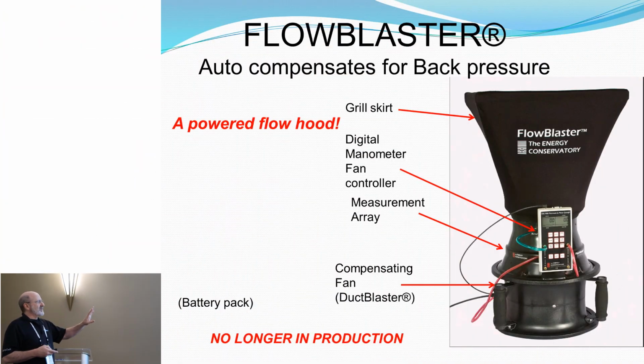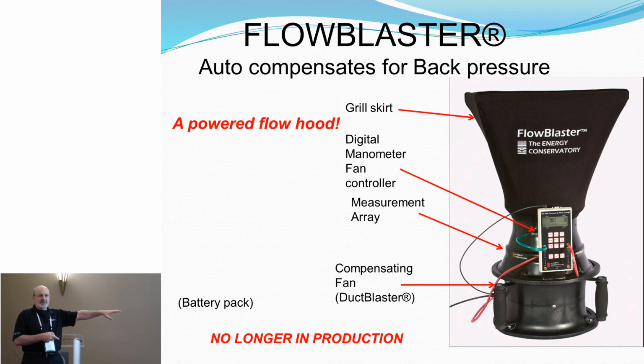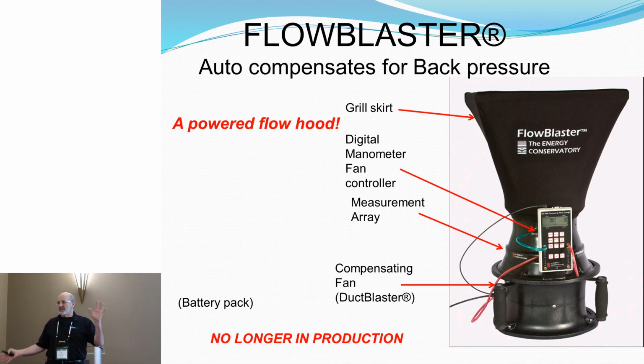I don't have time to show the comparison spreadsheet, but here's an illustration of the powered flow hood. We talked about it before. Basically a fan with a measurement grid, a manometer that will tell you the pressure under the hood. So the fan can run at the right speed to give you 0 pressure under the hood. So it looks like the room pressure. There's no delta P between the hood and the room.